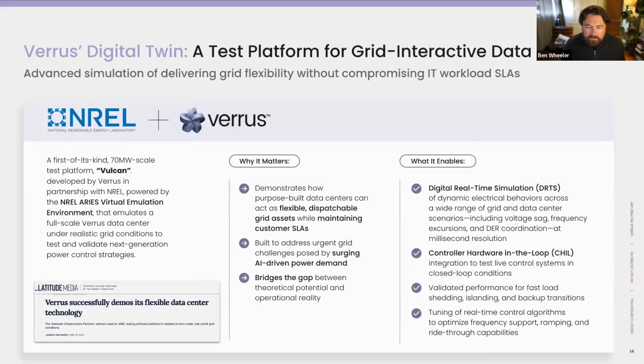One thing germane to the utility industry: as I mentioned, we're a relatively new company building our first data centers now. In parallel, we've developed a digital twin 70 megawatt simulation model and a hardware-in-the-loop testing model of our data center design at NREL, on their campus in Golden, Colorado. We've been able to prove a lot of the utility-facing capabilities we talked about—demand response and running primarily off batteries during a utility outage—in that model.